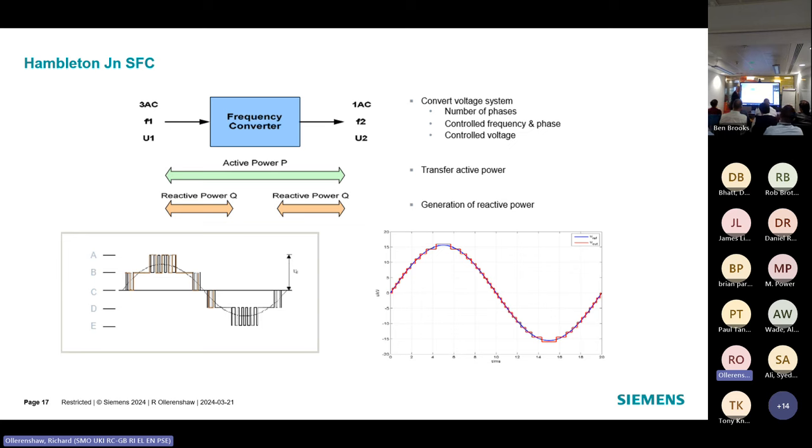People like to say, and you'll see some press releases saying, it's the first multi-level modular 25 kV SFC in the world. It's actually not. Wildenrath in Germany, which has the test loop, got there first. But the people who write press releases don't seem to have noticed that one. We have chains of IGBTs. IGBTs are simply faster switching, more efficient, more modern versions of thyristors.